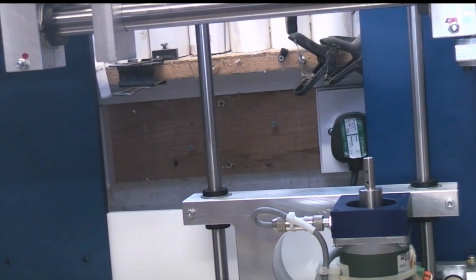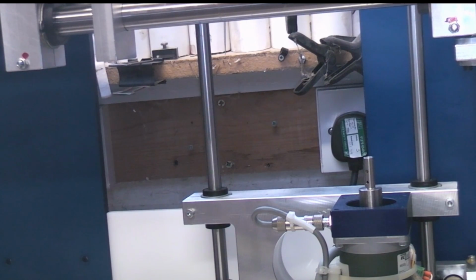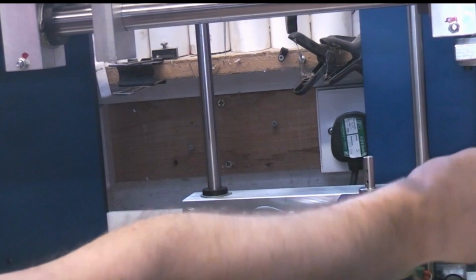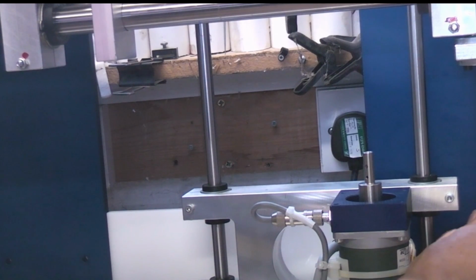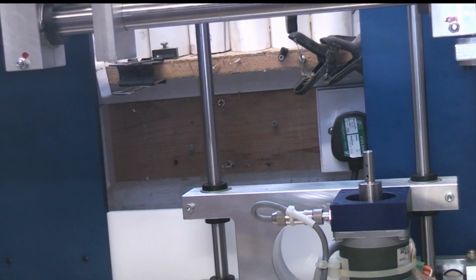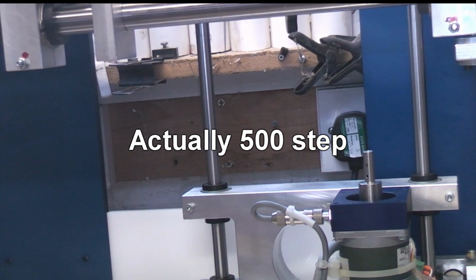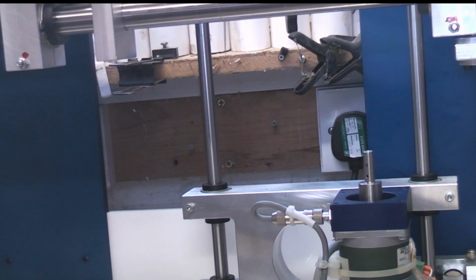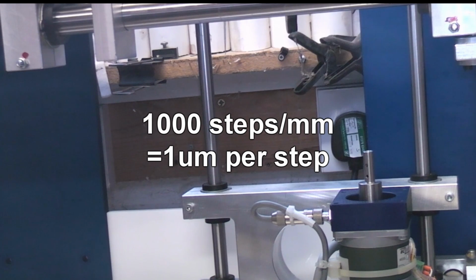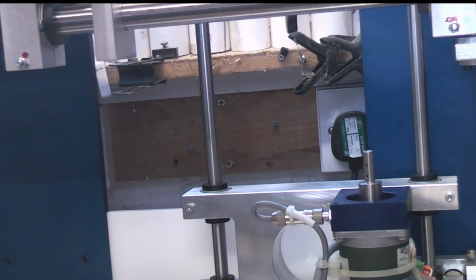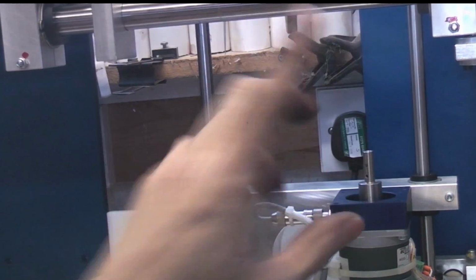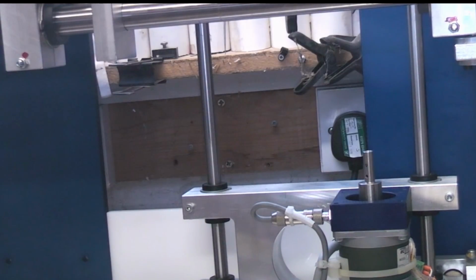And then we've got the vertical thing, which does two things. Firstly, it moves the sample up into this assembly, but then it gives you this very fine vertical control. According to the documentation, it will do slices down to 6 microns. I haven't measured it, but that feels like probably about a 0.5 millimetre lead screw, and then you've probably got a 400 step motor. So that gives you 800 steps per millimetre. That obviously gives you very fine resolution on that slice axis, and then this stepper motor here just rotates the sample within each slice.